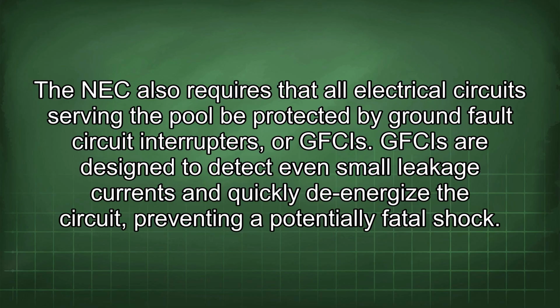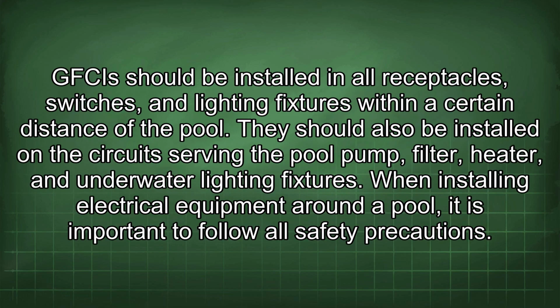The NEC also requires that all electrical circuits serving the pool be protected by ground fault circuit interrupters, or GFCIs. GFCIs are designed to detect even small leakage currents and quickly de-energize the circuit, preventing a potentially fatal shock. GFCIs should be installed in all receptacles, switches, and lighting fixtures within a certain distance of the pool. They should also be installed on the circuits serving the pool pump, filter, heater, and underwater lighting fixtures. When installing electrical equipment around a pool, it is important to follow all safety precautions.